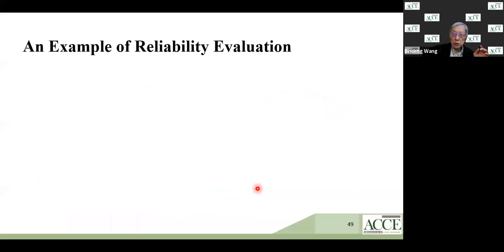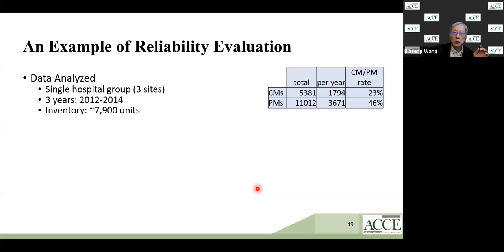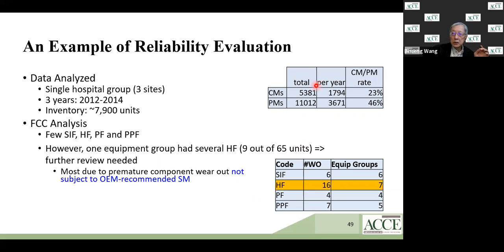Okay, so let me show you an example. We used a small hospital group, 3 sites, 8,000 pieces of equipment, and we were analyzing corrective maintenance and scheduled maintenance there, and we found there was a high number of hidden failures. And we said, well, that's very strange. What's wrong with this piece of equipment? And then we found out that this was something called an oxygen concentrator that was used for elderly patients in a long-term care facility. And we were performing maintenance exactly as recommended by the manufacturer.